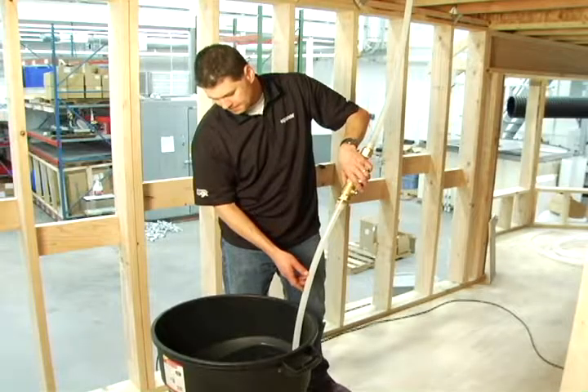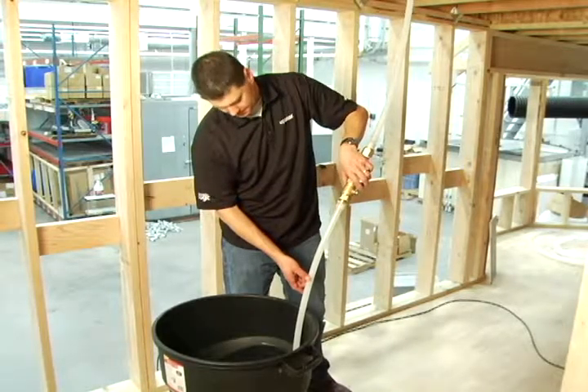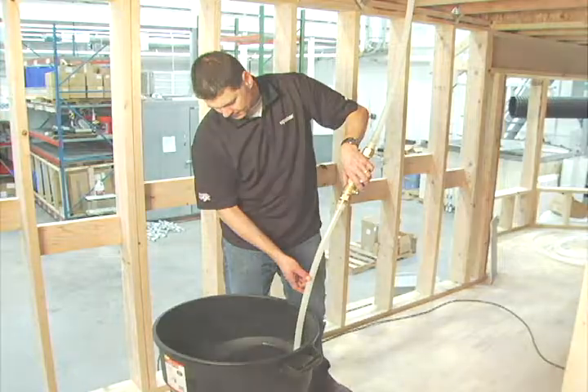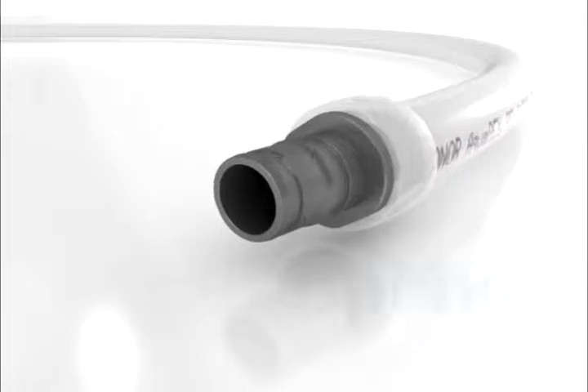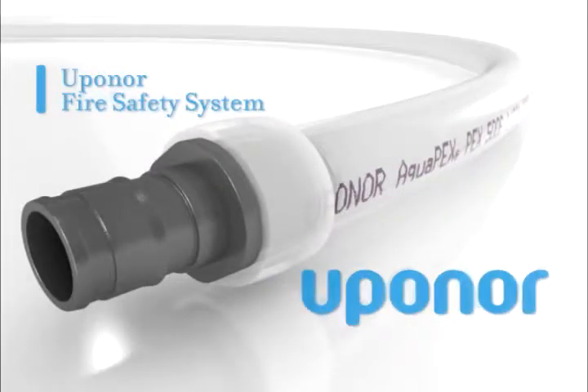You've now completed the installation of an Uponor AquaSAFE multipurpose sprinkler system with fewer connections, no cements or glues, and no backflow preventer. And, since no annual inspection or maintenance is required, you can be confident that you've installed the most effective and efficient sprinkler system available.